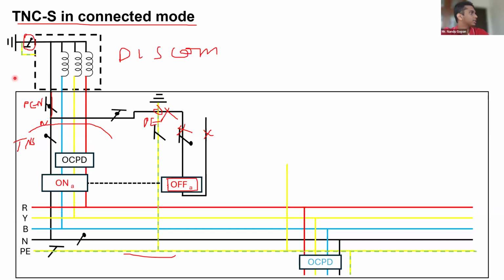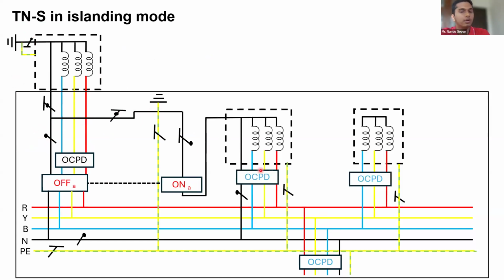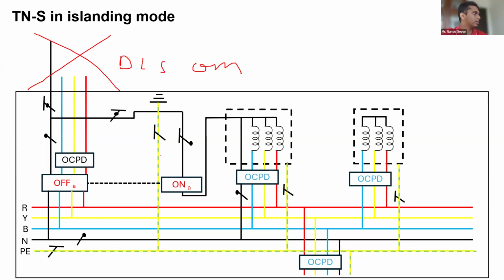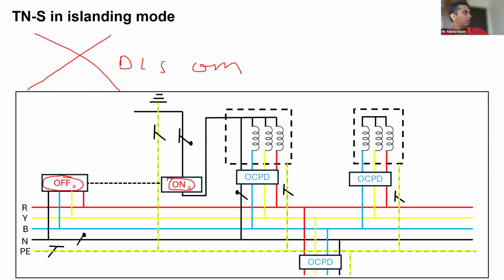Now, what happens is, what if, how does it change to a TNS system in islanding mode? In islanding mode, this system won't be there. This transformer won't be there. This discom's transformer won't be there. So we can ignore a few things, for example these things that we can ignore. And since this is an islanding mode, this will be in off and this will be in on conditions. So we can take all the things which are there on the top. From here, we can take everything outside.